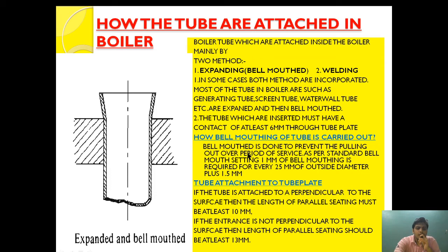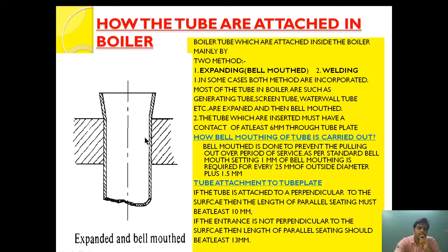Bell mouthing is done so that the tube doesn't get pulled out while it is in service. As per standard, 1 mm of bell mouth is required for every 25 mm of outside diameter plus 1.5 mm. So if the diameter is 25 mm, then the bell mouthing will be 1 + 1.5 mm of the diameter.